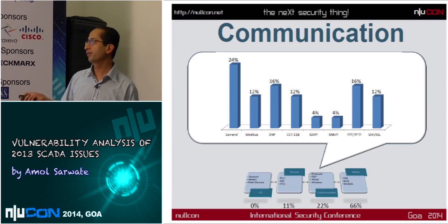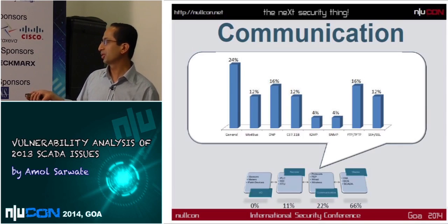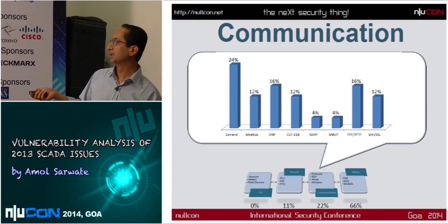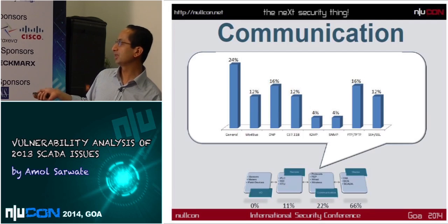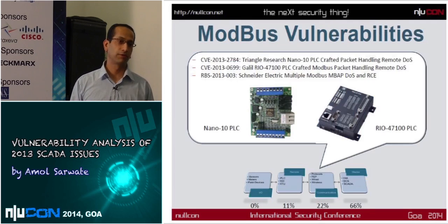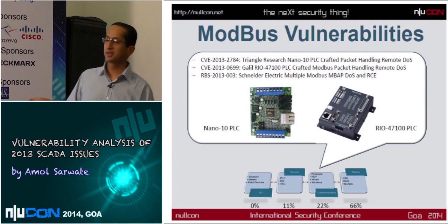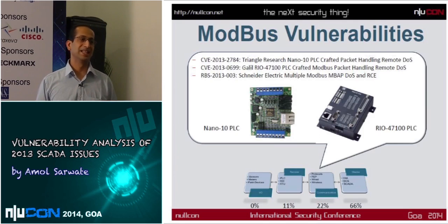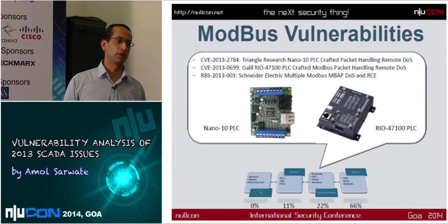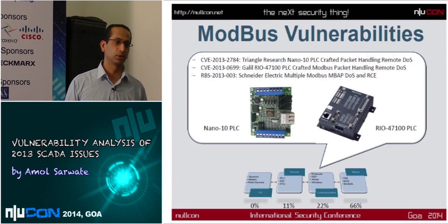So here you have different SCADA protocols, ModBus, DNP3, IGMP. IGMP is not really a SCADA protocol, it's a generic protocol, but these few are the SCADA protocols, these few are our normal protocols that we use every day. And this is just a distribution of how vulnerabilities look like. So basically for ModBus and DNP3, ModBus is used mostly in industrial controls. DNP3 was designed from the ground up for the electrical system, and it's used mostly in North and South America for controlling the electrical grid.